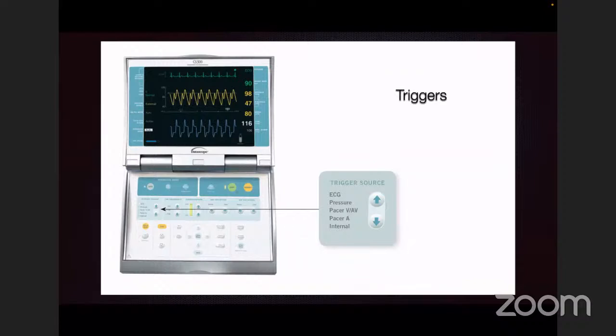If the patient is paced, the pacemaker spike can also be used as a trigger. There is another mode called an internal mode. Internal mode is when the patient has arrested, when there is absolutely no cardiac output. When you're giving CPR, the IABP just keeps on pulsating at a preset rate between 80 to 120. You can set the rate at whatever rate you're comfortable with.